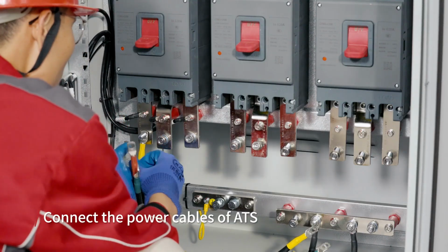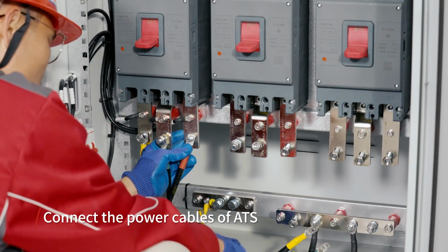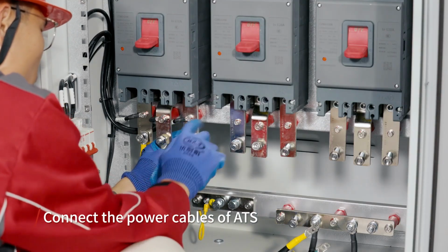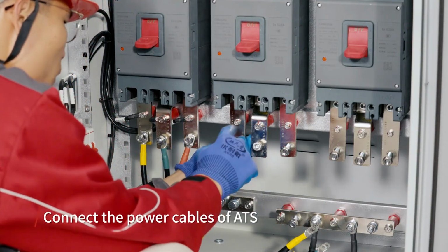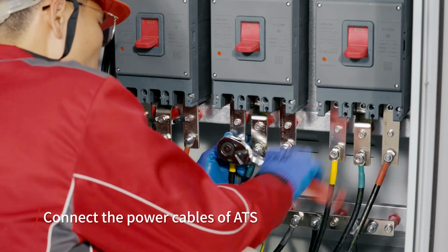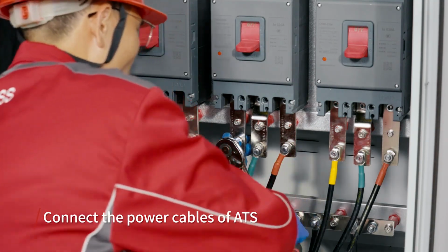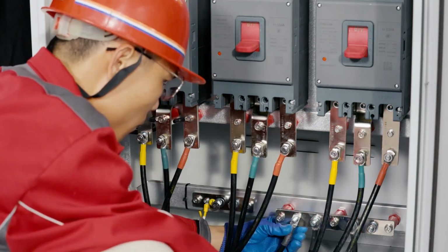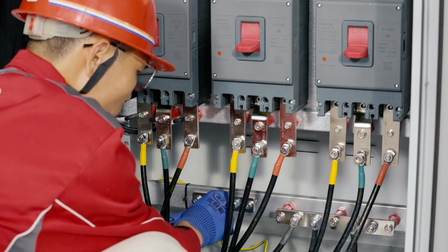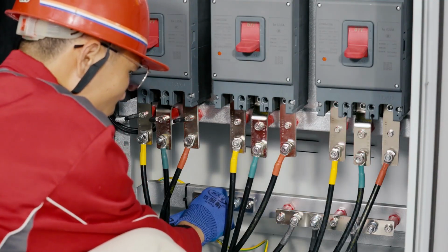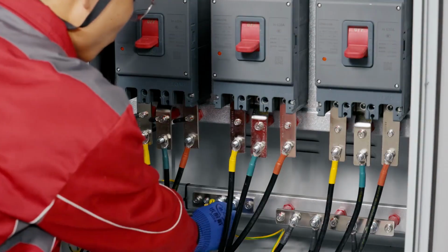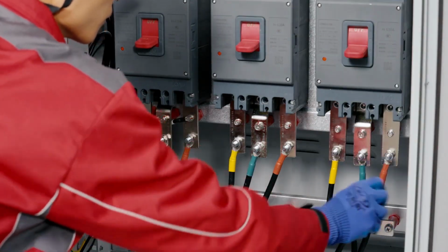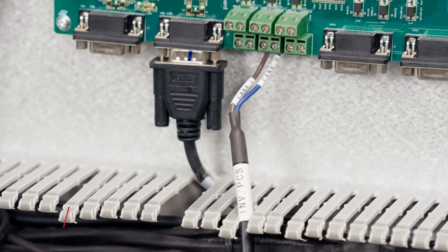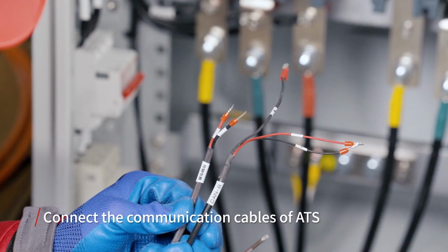Connect the grid cables to the grid breaker of ATESS, the HPS output terminal of ATESS to the grid breaker of HPS, and the generator cables to the generator breaker of ATESS. Connect the N cables of grid and load to the N bar of HPS, and the PE cable to the PE bar of HPS. Check if the wiring is correct and firm. Connect the HPS CAN bus, notice H and L.